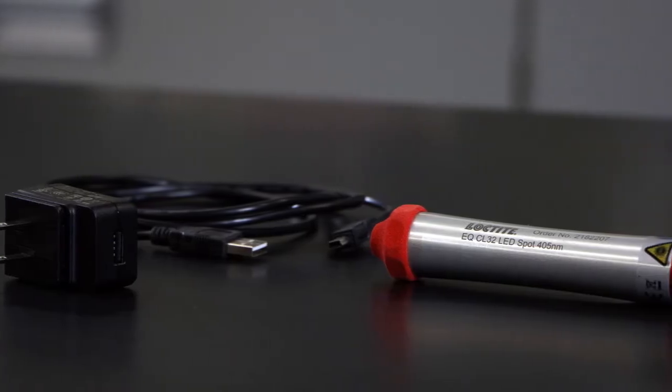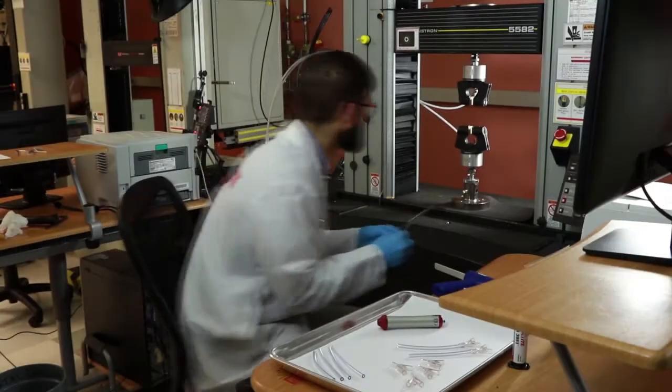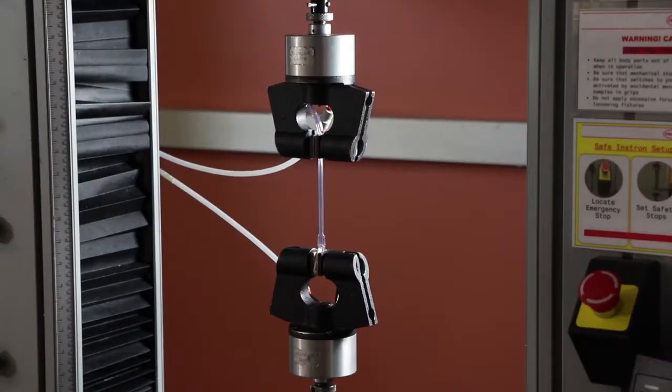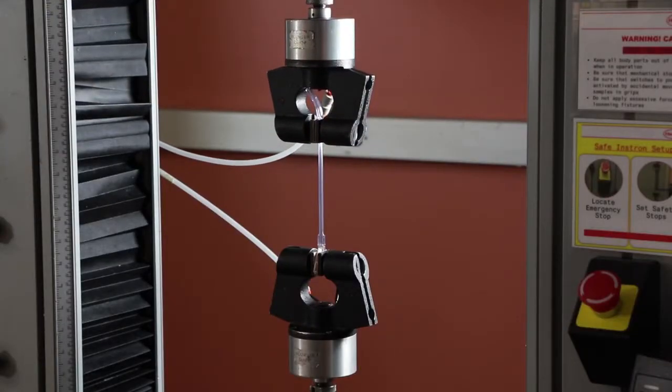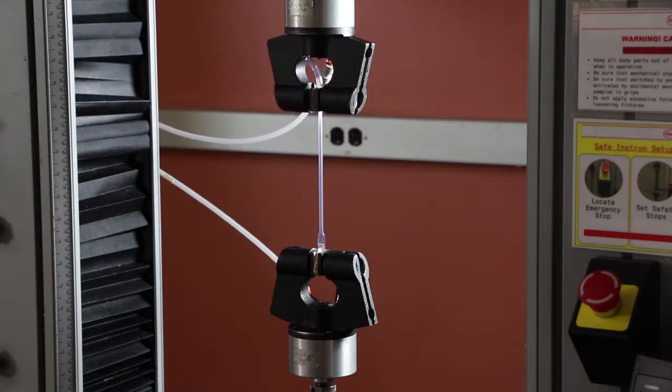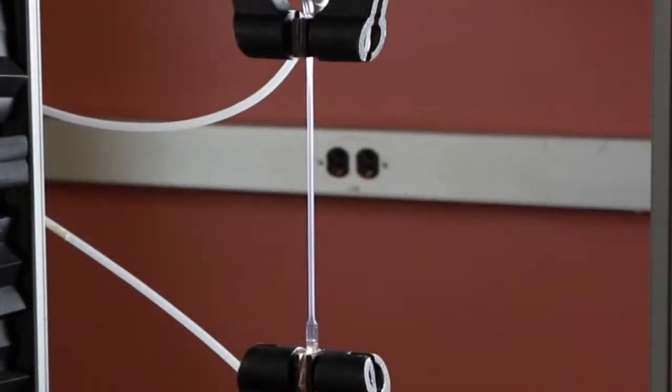The Instron tester is used to determine bond strength of the assembly in shear mode. The PVC tube stretches and elongates and the adhesive holds strong, eventually the weakened PVC tubing breaks while the bond holds strong.